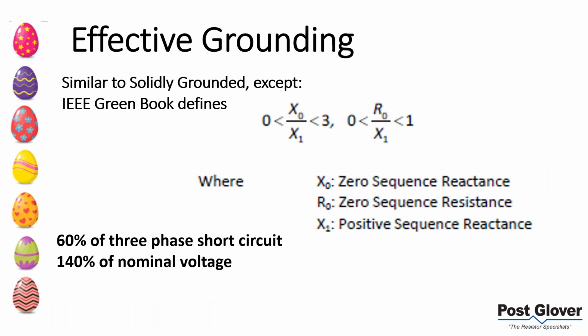Moving on to effective grounding. We need to talk about this because it's important in the renewable space, especially with wind and solar. It is essentially the same thing as solidly grounded, except you're going to have some kind of impedance. So it's a low impedance path, but not as low as solidly grounded. The Green Book defines it essentially as your zero sequence reactance over your positive sequence reactance. Really, this is more for reference. We don't need to talk about how you achieve this in a technical sense, but we will talk about it in a general sense. So you get the idea here.